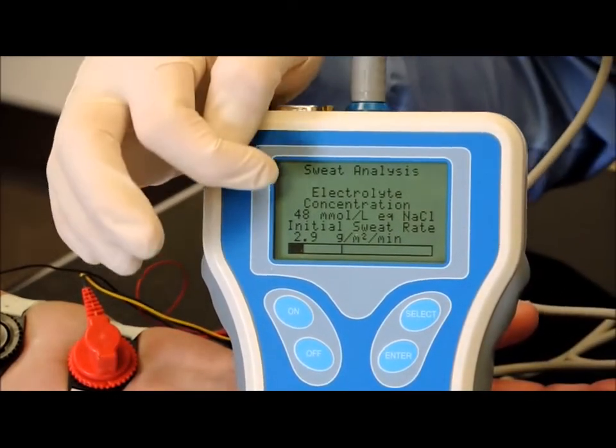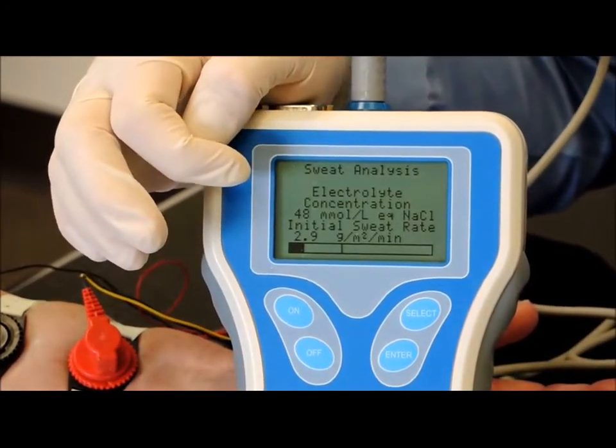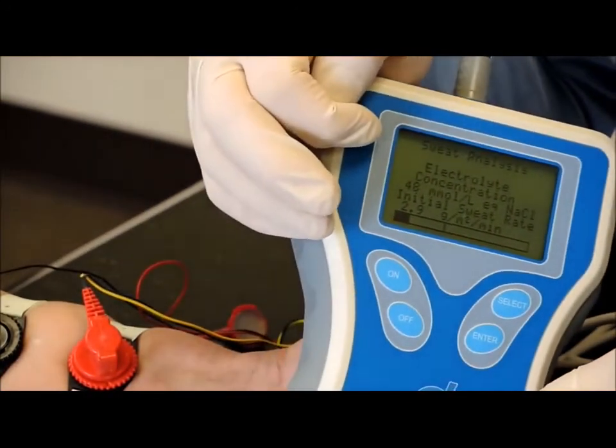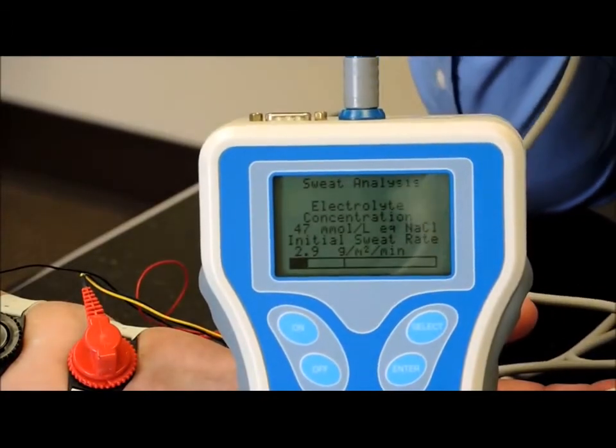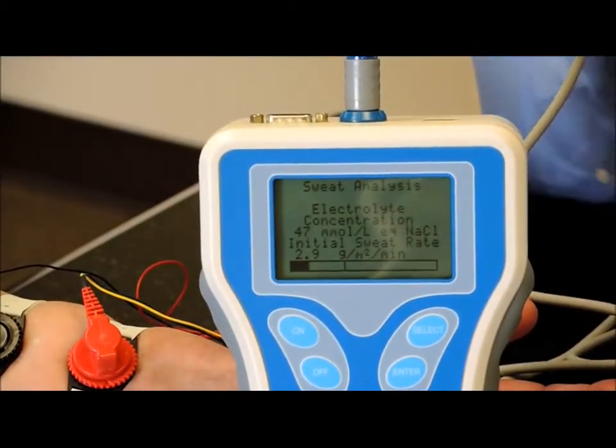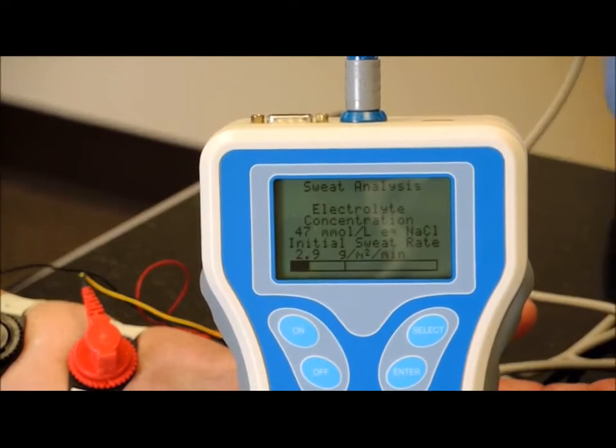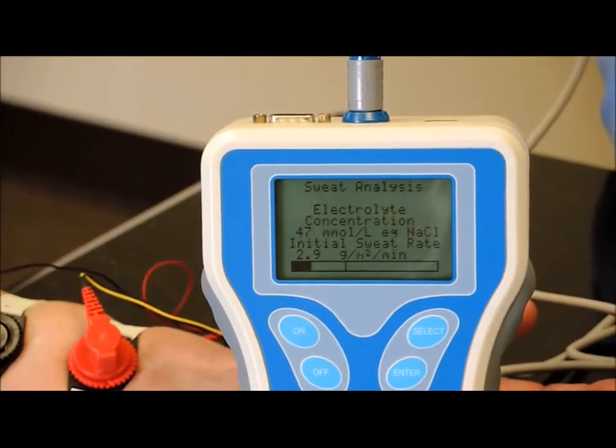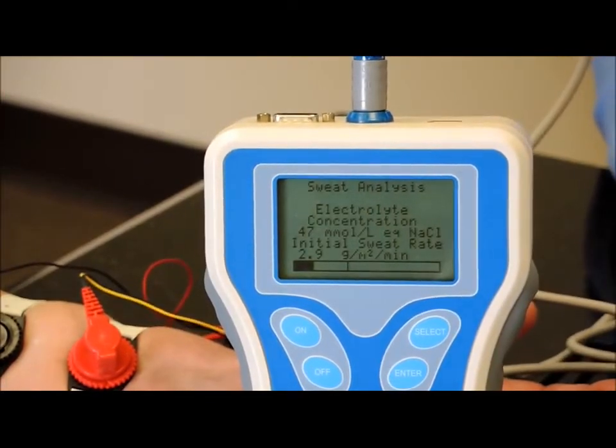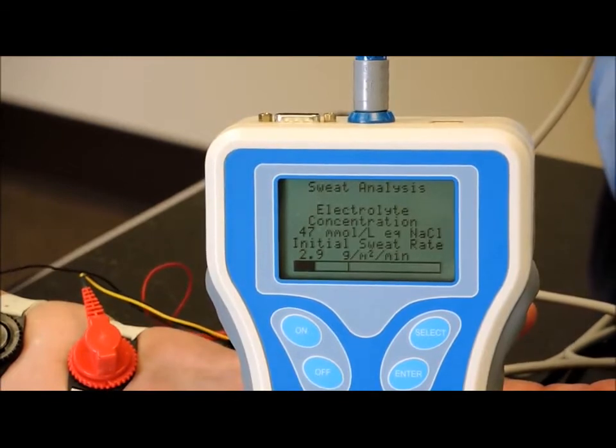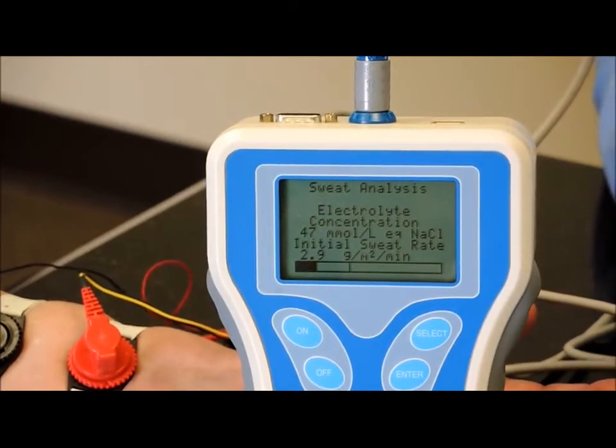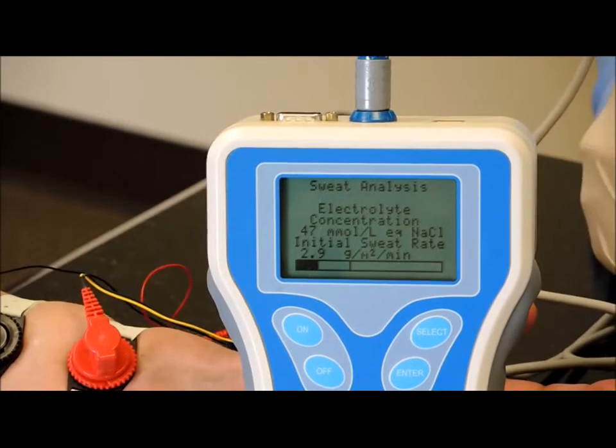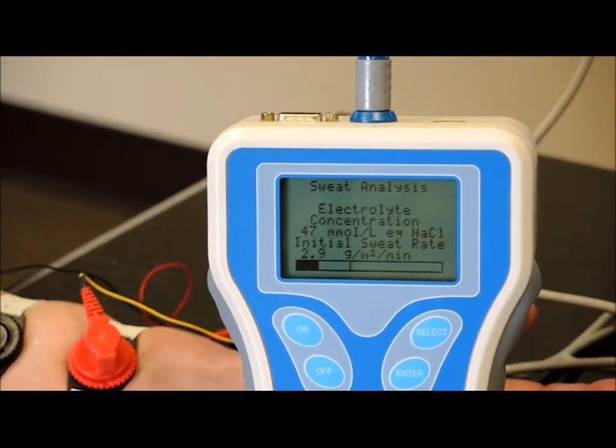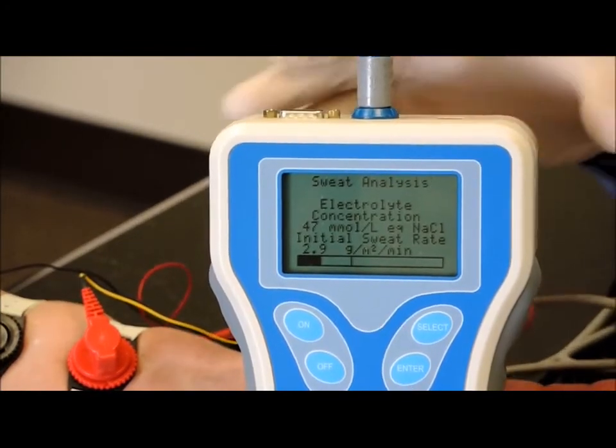Now you can see the conductivity reading, right now it's 47. Typically that reading will go down. The sweat that normally comes out first from a patient is more concentrated. It's just a biological variance that we all have, that sometimes the sweat is more concentrated with ions, and so you'll see the conductivity value be higher at first and go down.